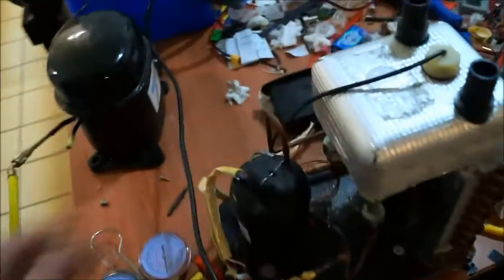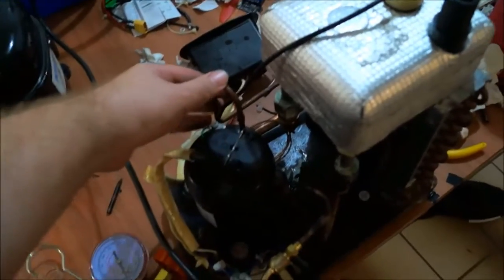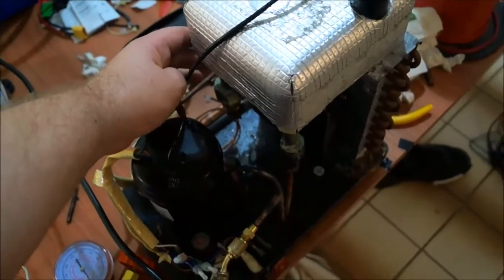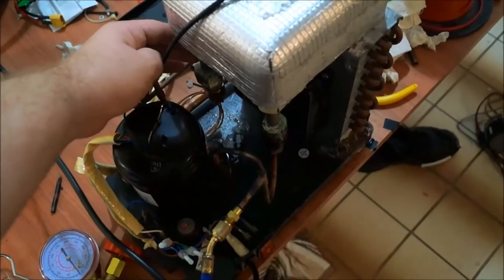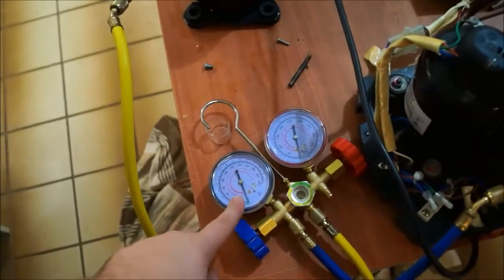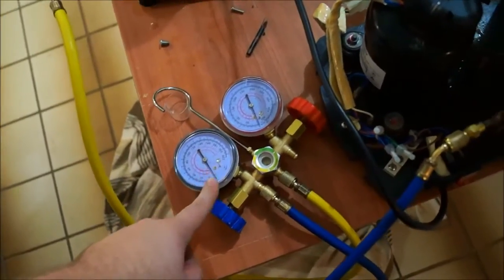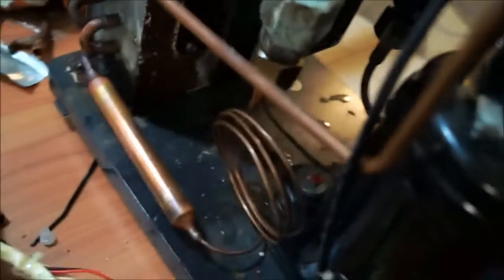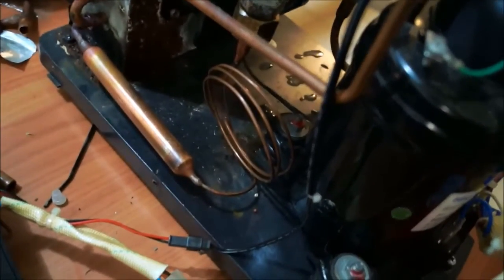First thing I noticed was the discharge line was getting crazy hot but I was getting basically very little cooling. I had the gauges connected as well and I noticed it was hardly getting above vacuum, so pretty quickly figured out that there was a blockage somewhere, probably in the capillary.